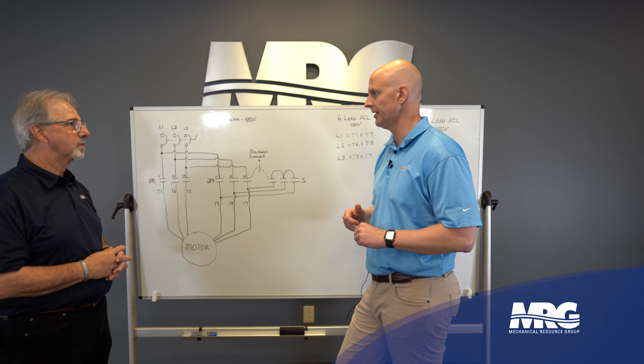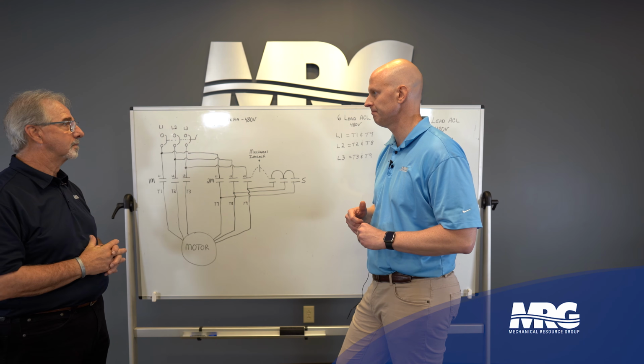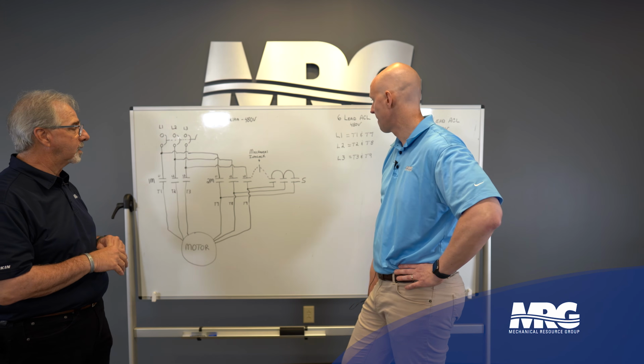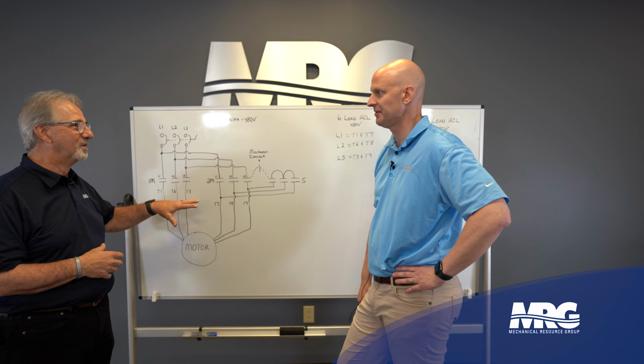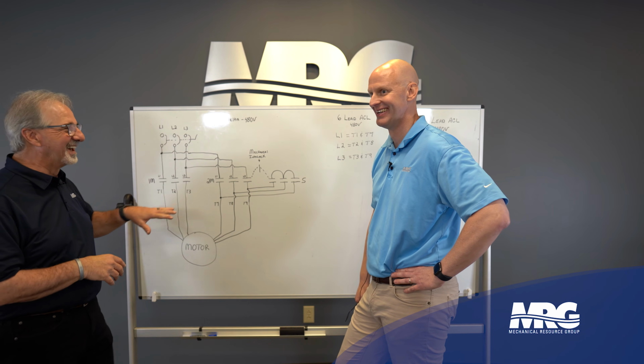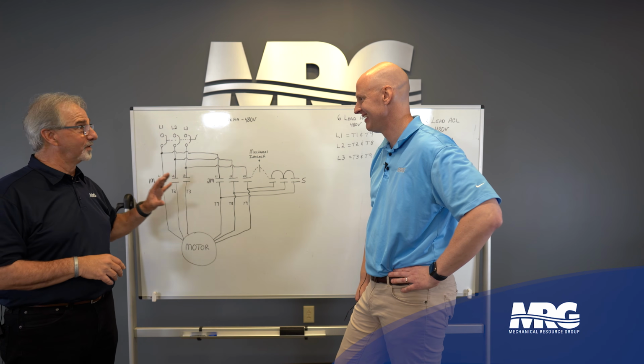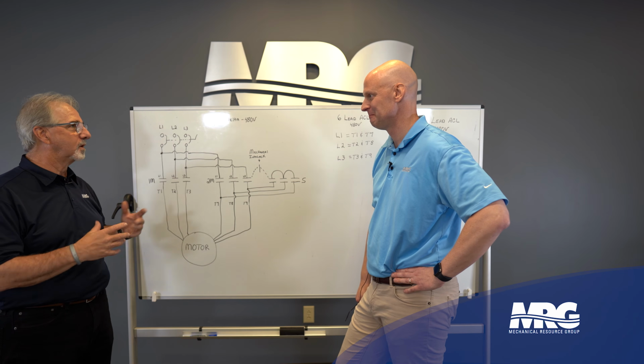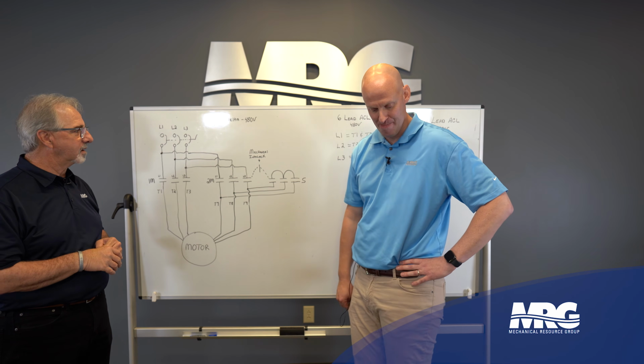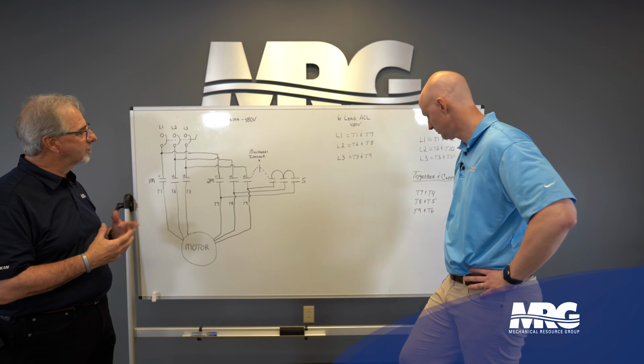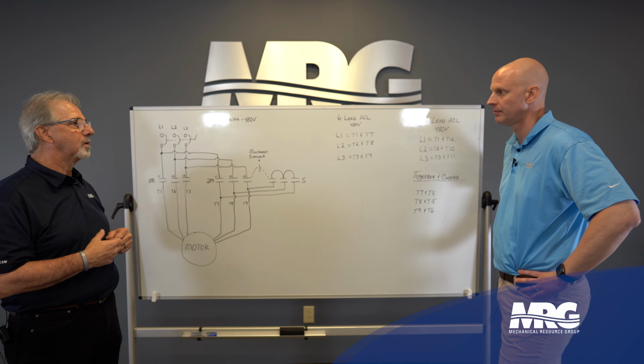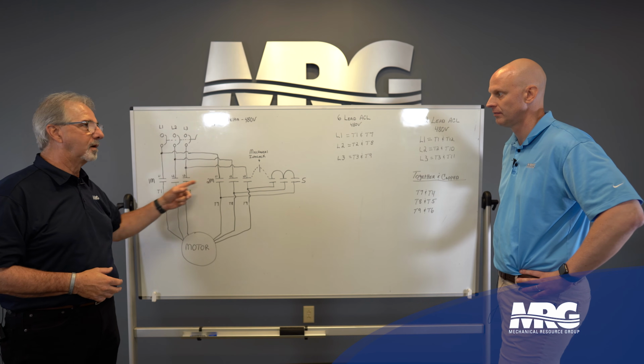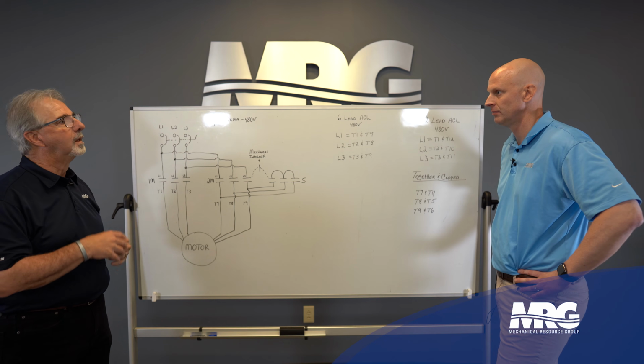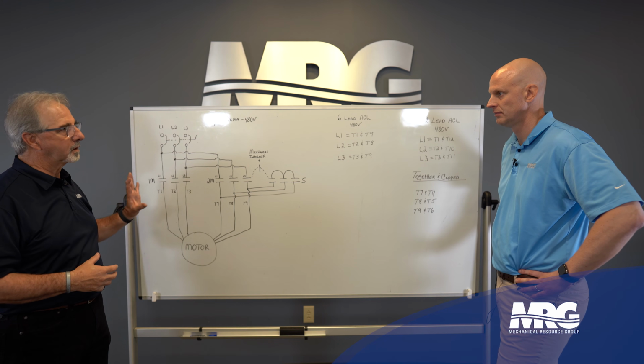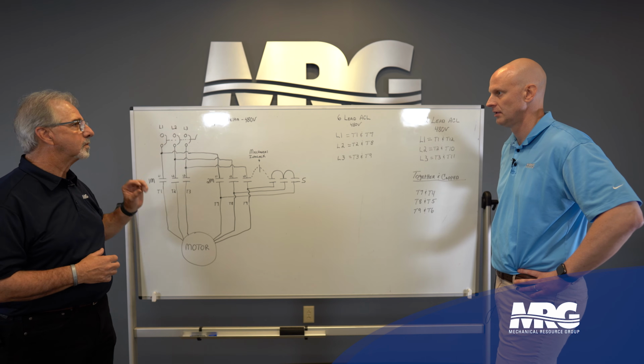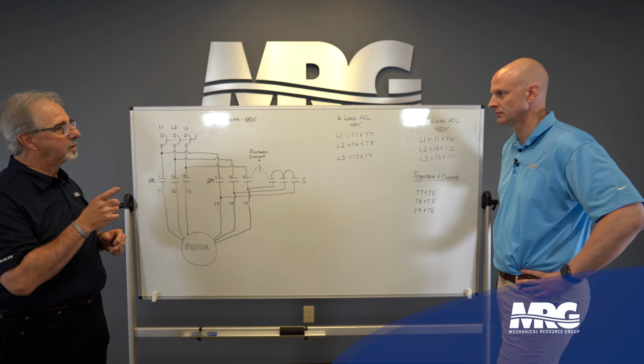Yeah, I can see how this could be really intimidating to a guy on the site. Oh yeah. He's scared to try it. Yeah, I mean, it really can be, because it doesn't take much. That's a religious experience. Yes, it is. It doesn't take much of a mistake to cause a flame. Yeah. And when you're talking about currents in the 1200 amp, 1300 amp range, it can get really ugly really quick. So we want to make sure that we connect our motor correctly, because not only are we going to damage the motor, we're also going to damage our components. We're going to fry the contacts and the contactors, and they have to be replaced. And so it's really, really important that you pay attention to this. Now, most chillers that we deal with are 6 leads, but we do have 12 lead.